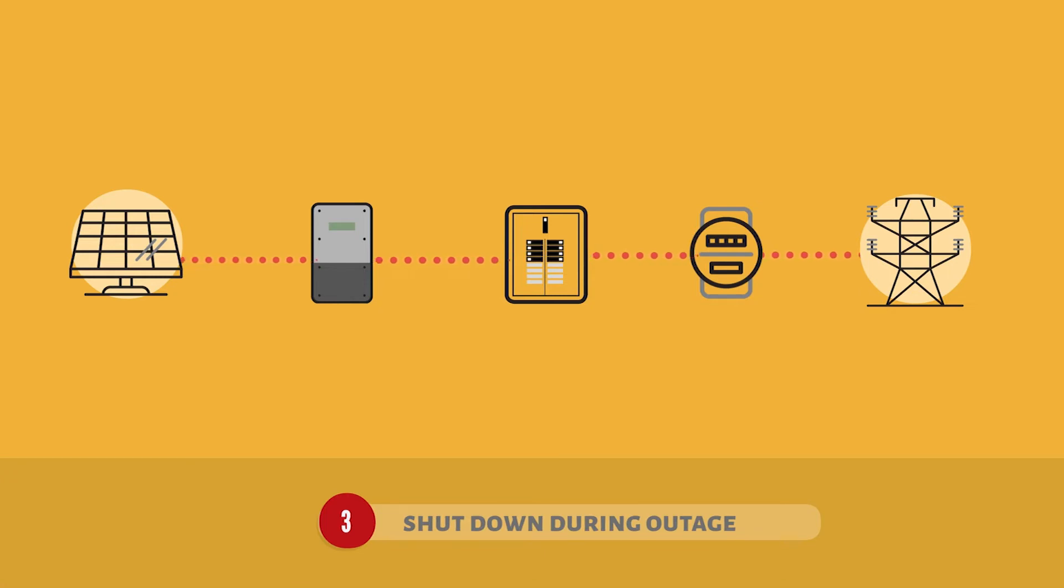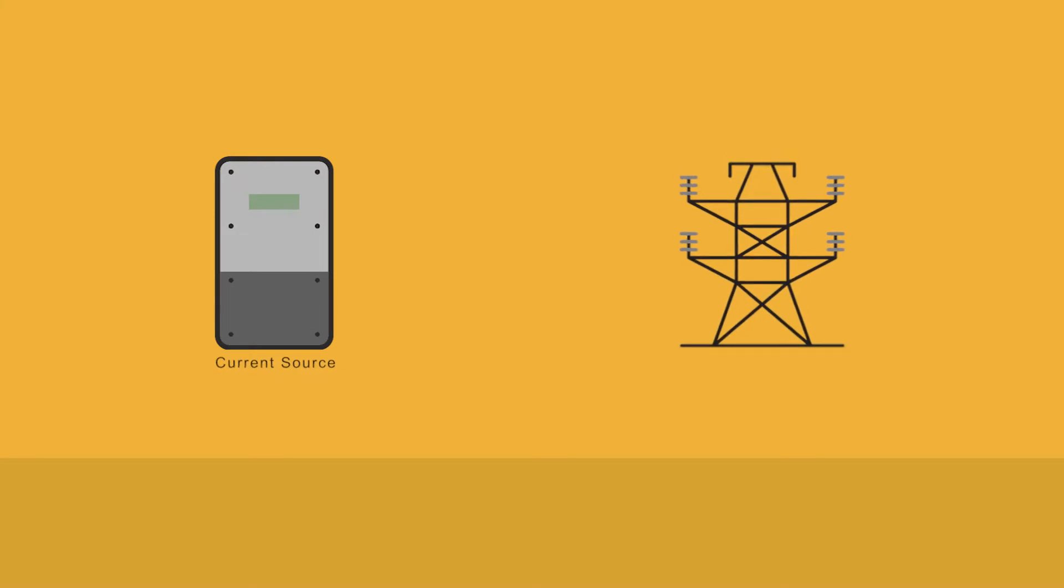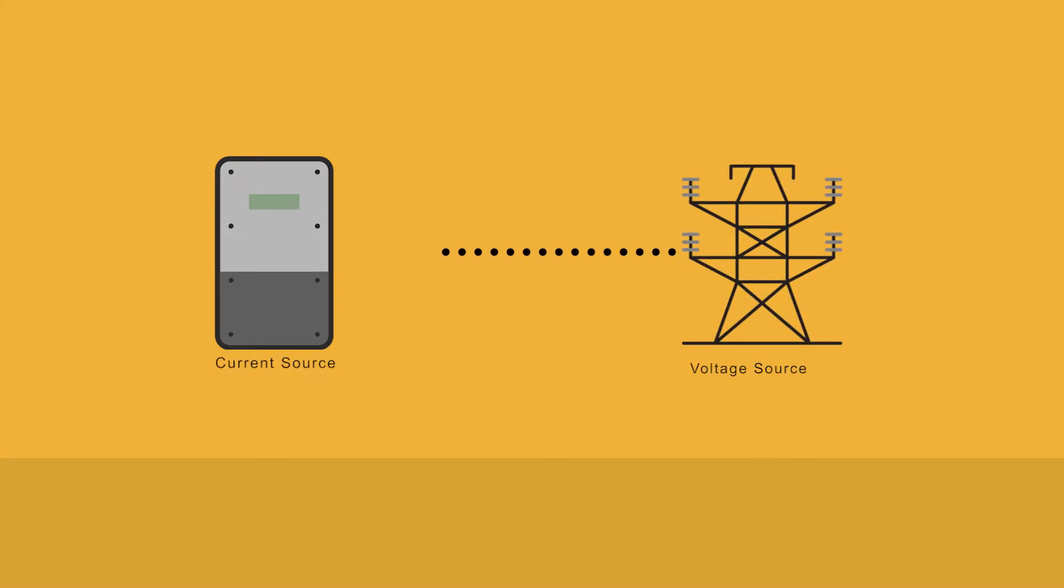And third, in the event of a power outage, the grid-tied inverter is required to shut down and cease solar production. As noted, a voltage source is required for the grid-tied inverter to work. This is because grid-tied inverters are a current source, meaning they are not designed to create their own voltage signal.